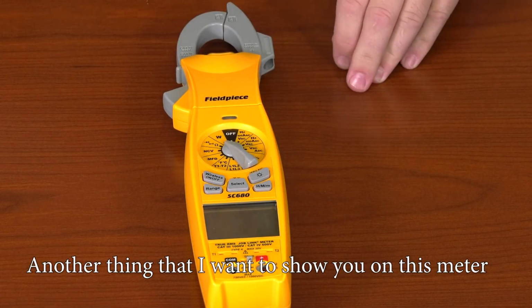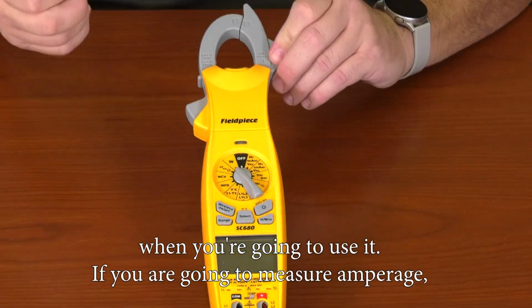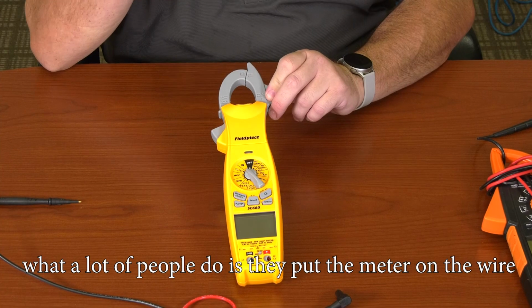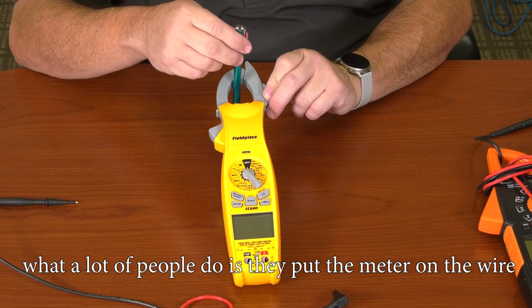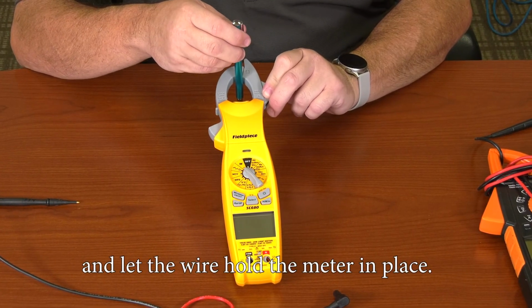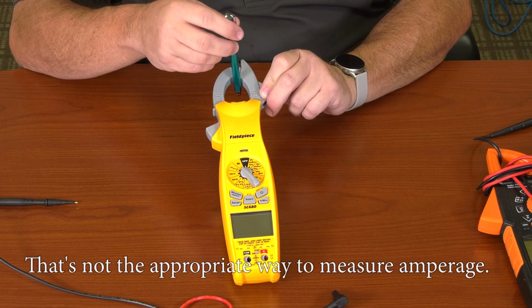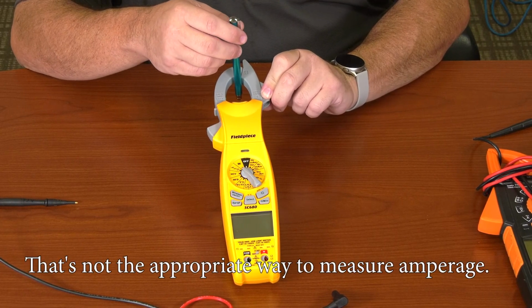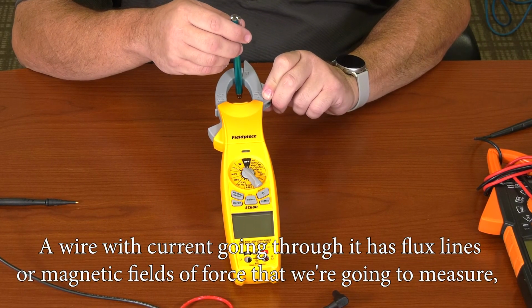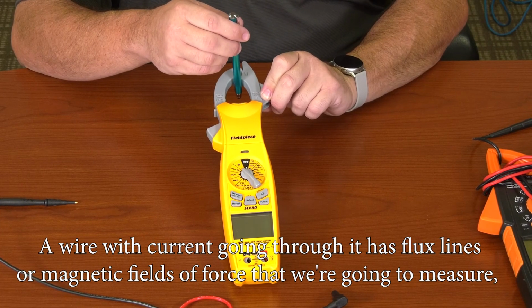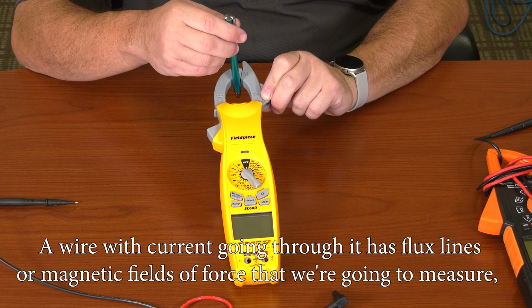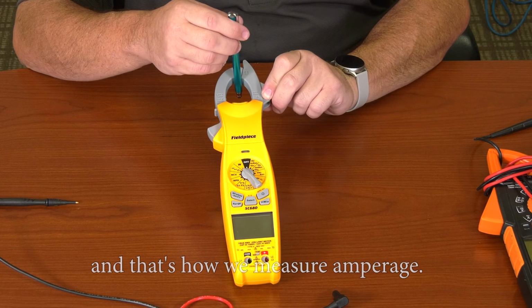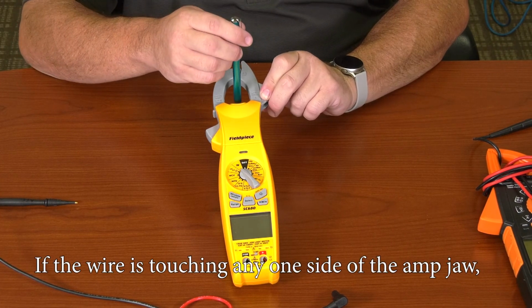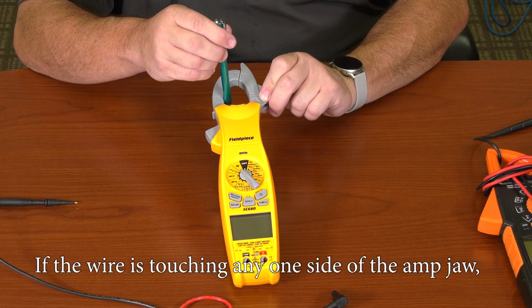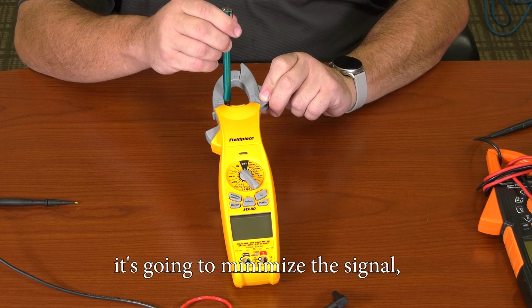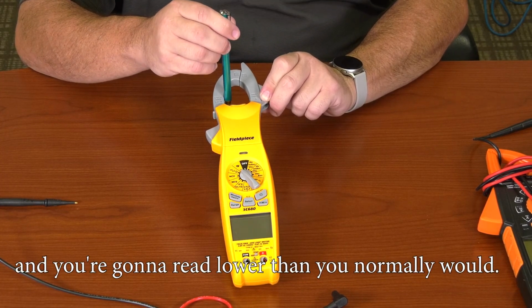Other thing that I want to show you on this meter when you're going to use it. If you are going to measure amperage, what a lot of people do is they put the meter on the wire and let the wire hold the meter in place. That's not the appropriate way to measure amperage. A wire with current going through it has flux lines or magnetic fields of force that we're going to measure, and that's how we measure amperage. If the wire is touching any one side of the amp jaw, it's going to minimize the signal and you're going to read lower than you normally would.